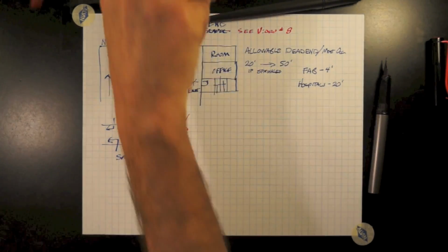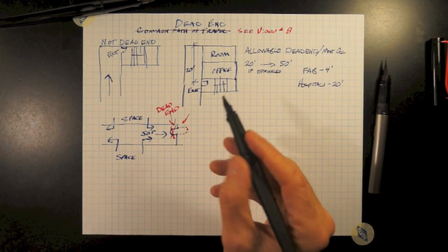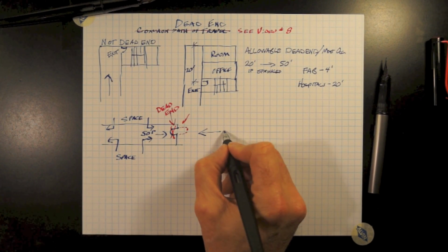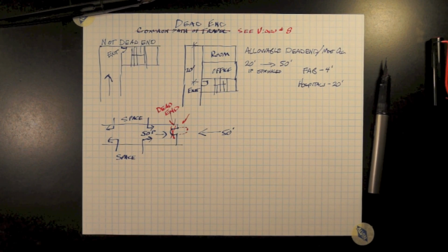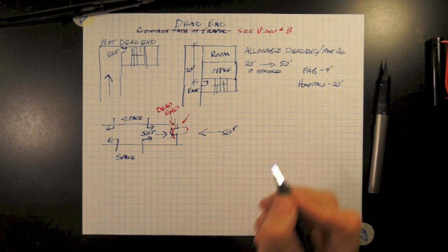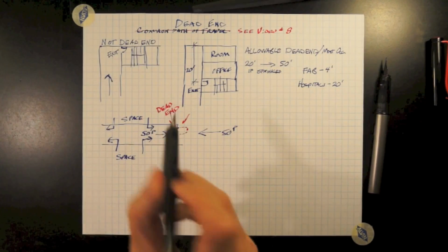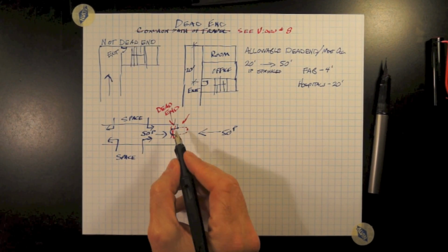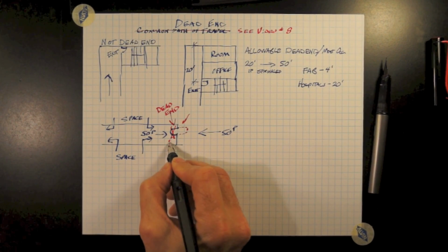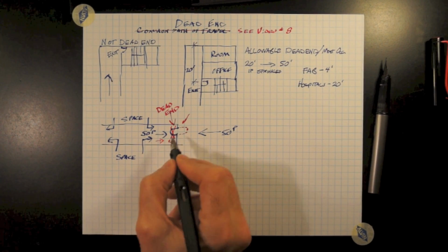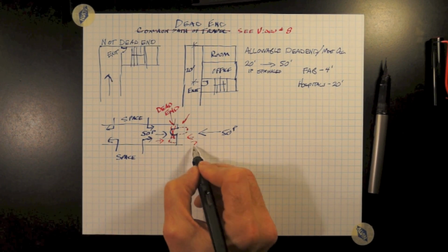Now, let's take into consideration if it's a large enough office space or such, there might be 50 people traveling toward that other side of the door. So a consideration of a pair of cross-corridor doors may be considered to prevent it from being a dead end. It will be a dead end if the door does not swing in the direction of travel.